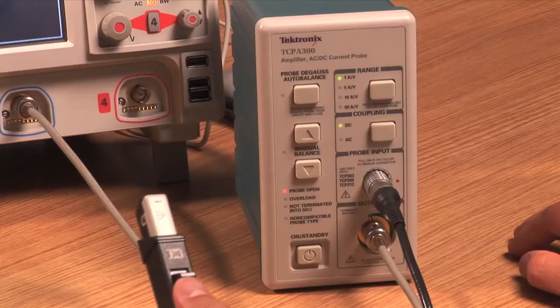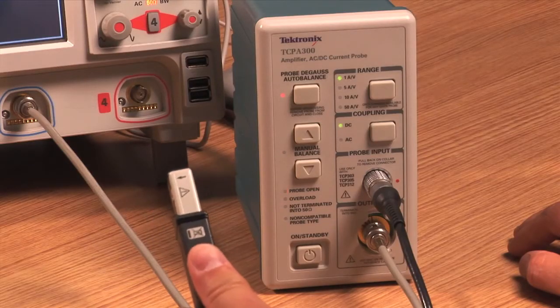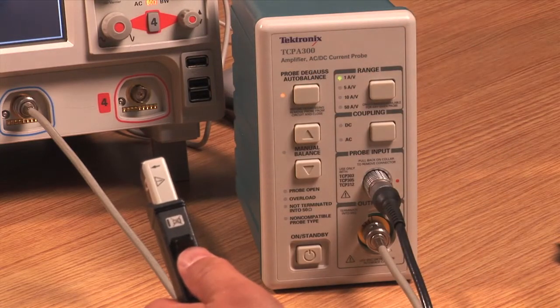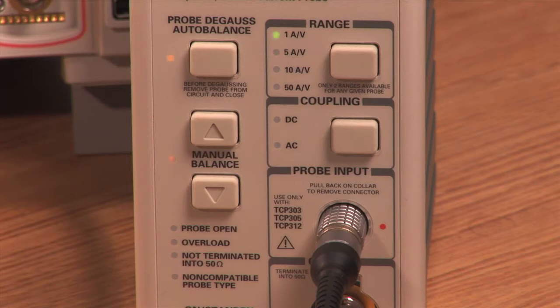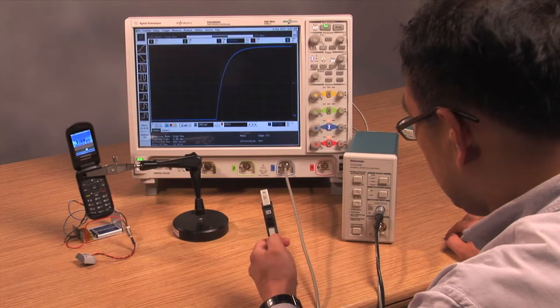Also, to acquire a more accurate measurement, an engineer would have to routinely degauss the probe to remove residual magnetism from the probe core and to help compensate for any DC offset. This extra calibration procedure makes the clamp-on current probe cumbersome to use.